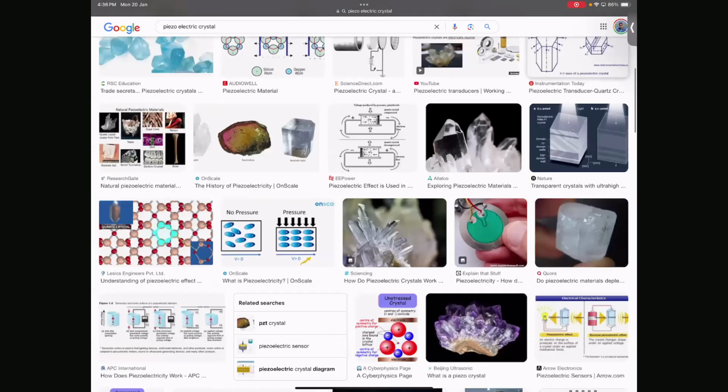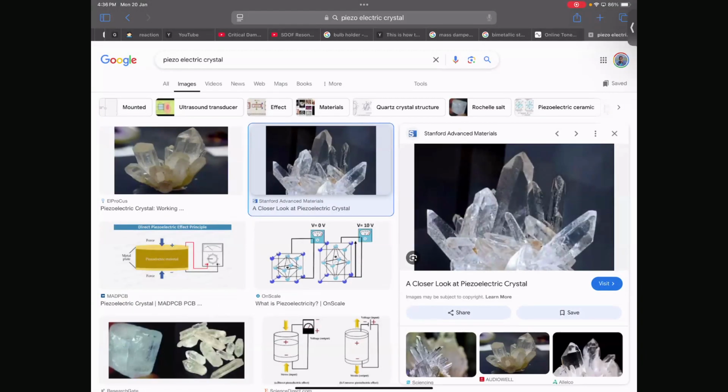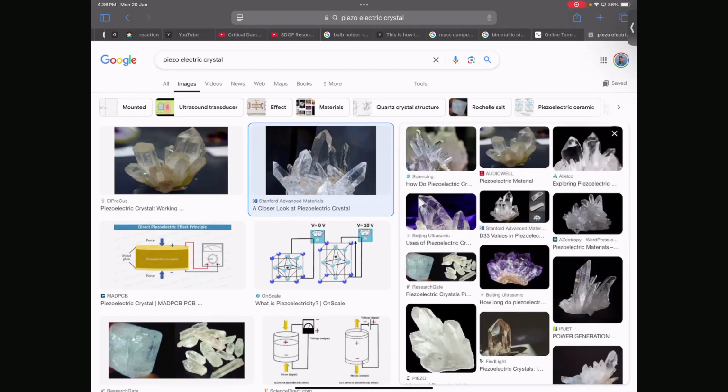The other direction, right? So these crystals form randomly, and from here you need to use a laser to cut them into thin slices, and there can't be any imperfection in the slice, like a fracture or anything, otherwise it won't work. That's why it's so expensive. Okay, these crystals are not that expensive, they were used in watches and are now used in many places, but when you want to use it in a transducer, it has to be very refined.